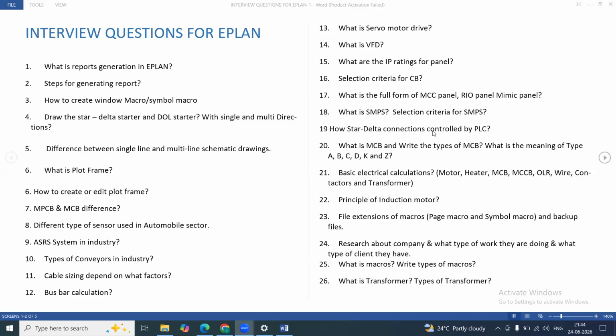How is star delta connection controlled by PLC? From the PLC we have to control three relays, and with the help of those three relays we control three contactors, and with the help of those three contactors we can control our star delta connections.